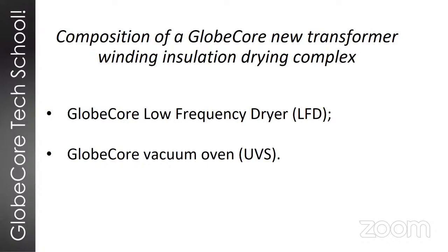The heating process and the evacuation process are completely automated. The duration of heating, the holding time under vacuum, and the number of cycles are all set by the operator according to the process requirements. So in the drying process, there's also the simultaneous process of heating the windings, extraction of water from solid insulation, and extraction of evaporated water from the vacuum chamber. Next slide, please.